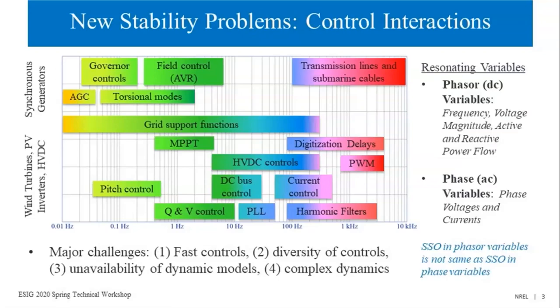So with the inverter-based resources and more converters in the power systems like HVDC converters, inverters, wind turbines, we are seeing more stability issues. Previously, the small signal stability was all about local and inter-area modes, very low frequency oscillations. But now we are seeing, because of diversity of controls, fast controls and inverters, a very rich kind of stability problems spanning over the entire frequency range. The main challenges are because of the diversity. Each manufacturer uses their own set of controls, dynamic models are unavailable, and all these controls are complex.